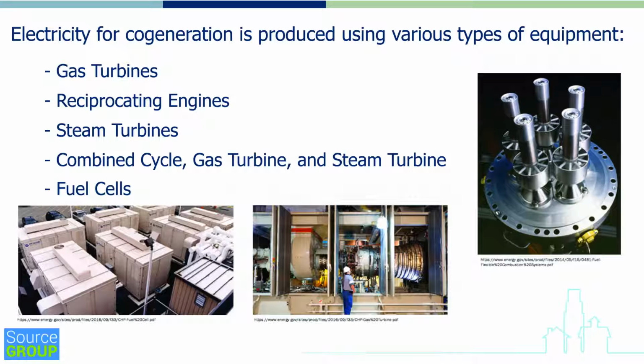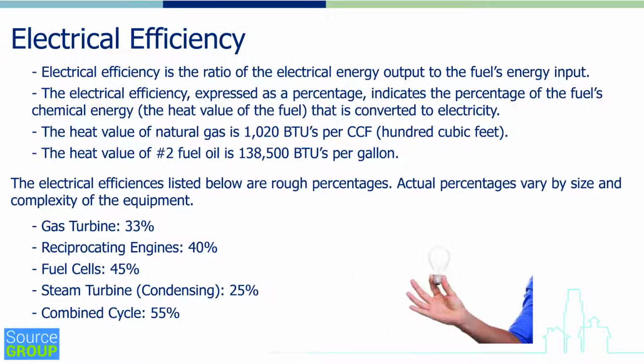Steam turbines, which take high pressure, superheated steam. It has to be superheated in order to remove moisture so that the water droplets don't corrode away the turbine blades. Combined cycle, which is a gas turbine that's used along with a steam turbine. The gas turbine exhaust recovers heat, which generates steam, and the steam is then used to drive a steam turbine. And fuel cells.